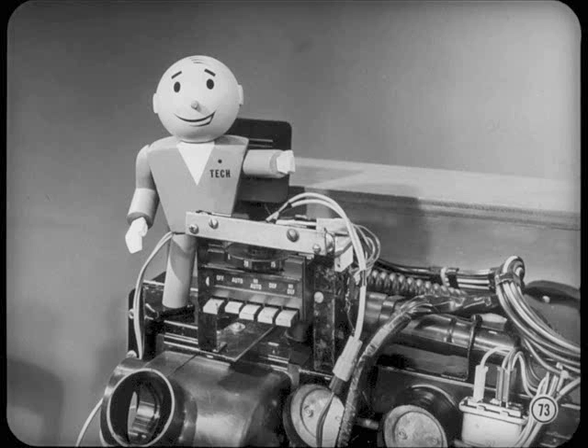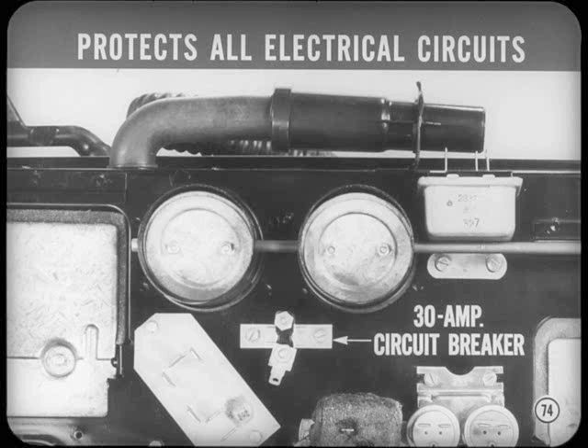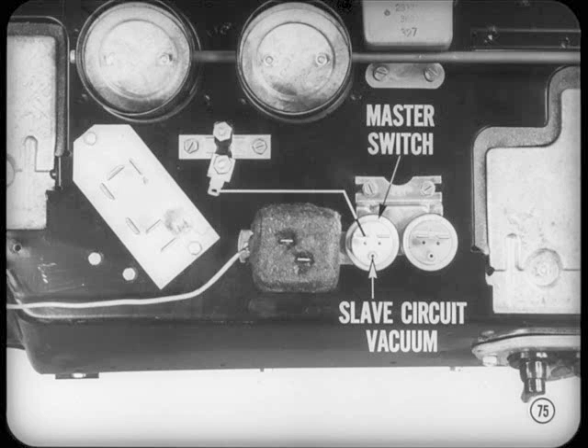I sure agree with that, Tech. The electrical blower circuit is protected by either a 30-amp circuit breaker or a 20-amp fuse. The sensor circuits, clutch circuit, and evaporator temperature regulator circuit are also protected by the same circuit breaker or a second fuse. But let's follow the blower circuit. Next in the blower circuit is the master switch. It keeps the blower from operating when the engine isn't running. The master switch is controlled by slave circuit vacuum and remains open until engine vacuum reaches about 8 inches.